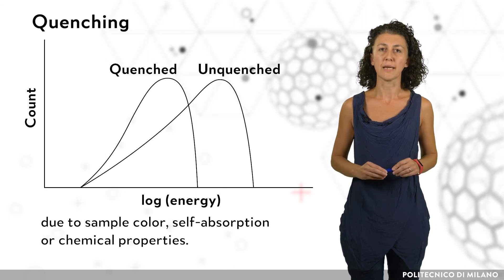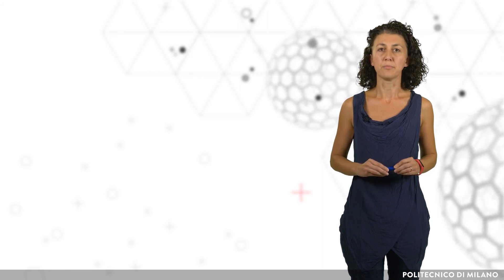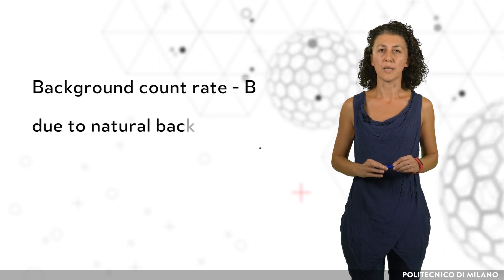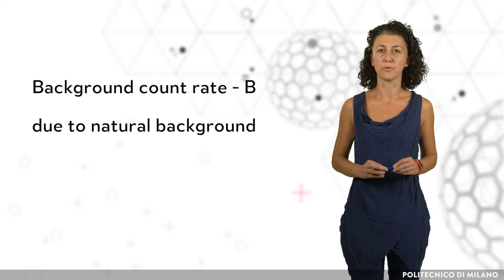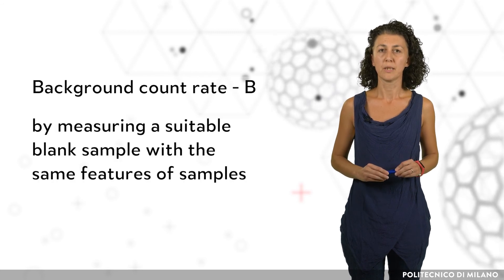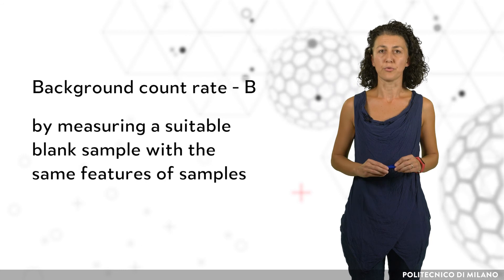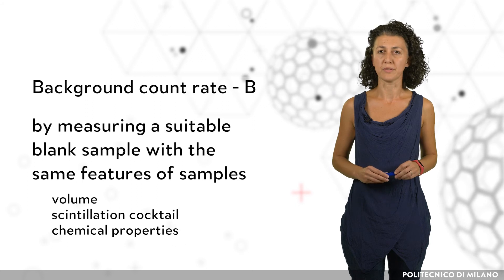To be able to evaluate an activity, which can be interpreted as mean activity, the background count rate due to natural radiation has to be determined by measuring a suitable blank sample. It has the same features of samples in terms of volume, scintillation cocktail, and chemical properties.